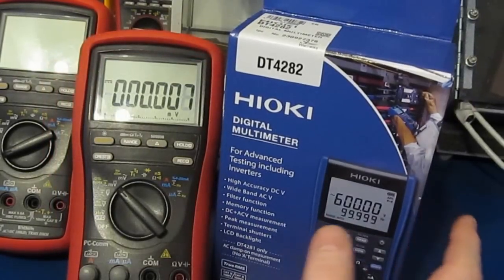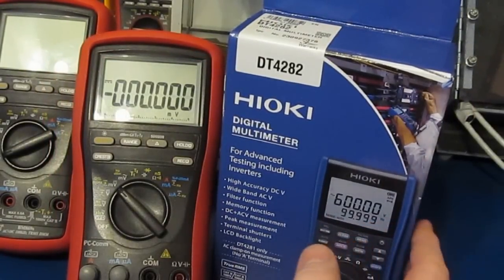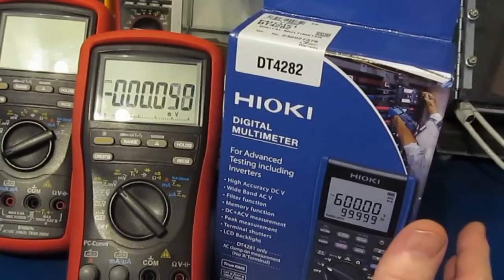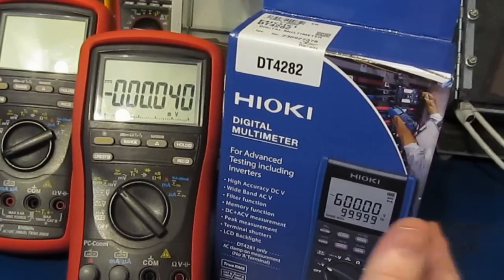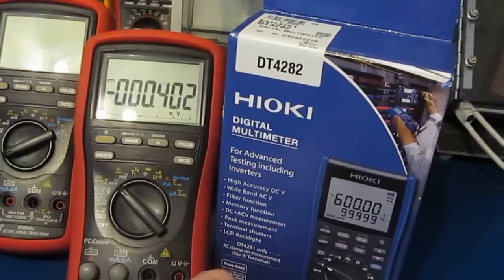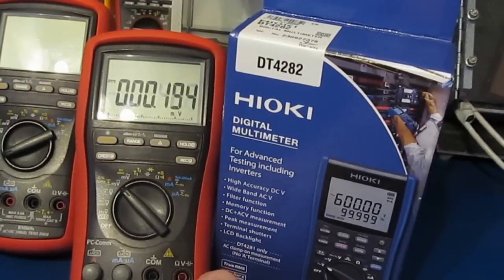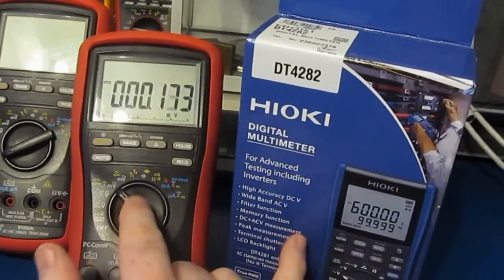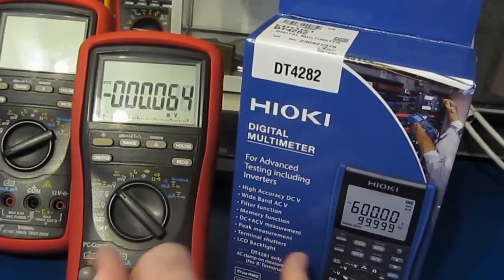In the 60 millivolt range, the input impedance of this meter is typically about a gigaohm, in parallel with 100 picofarads, where the Brymen's 500 millivolt range has a 10 megaohm input impedance in parallel with 60 picofarads. The documentation for these meters is all available online.